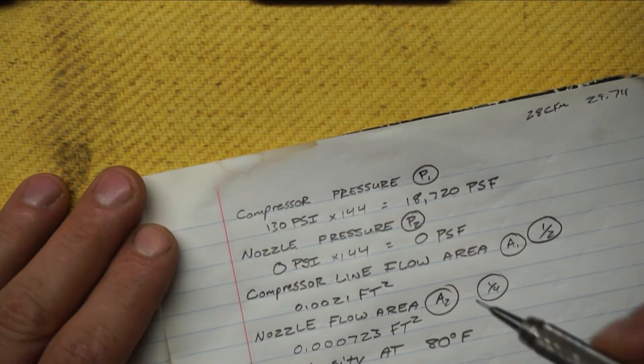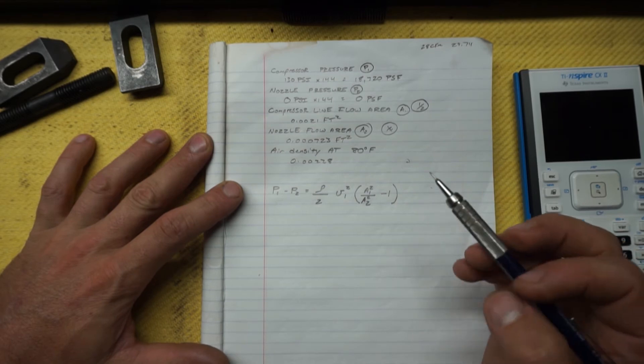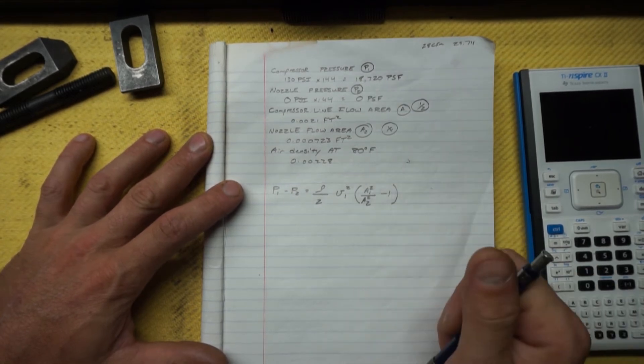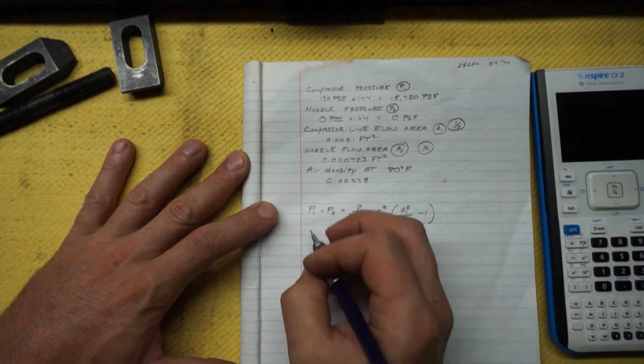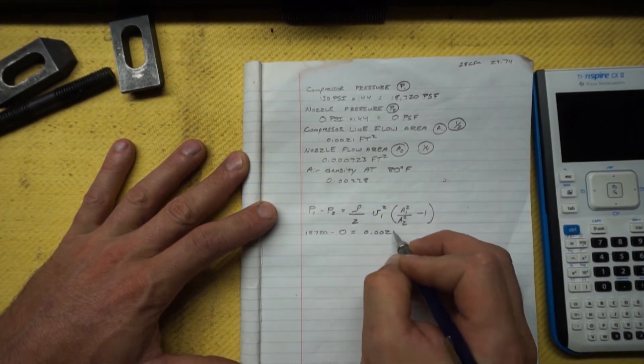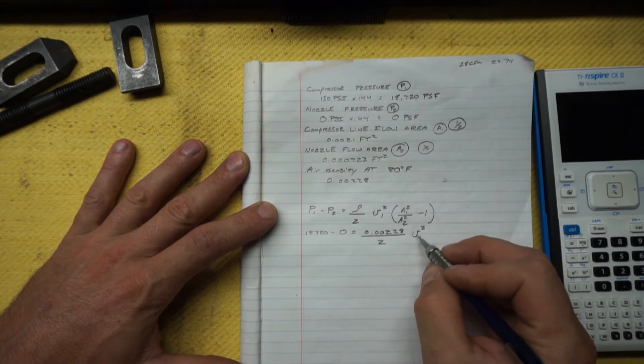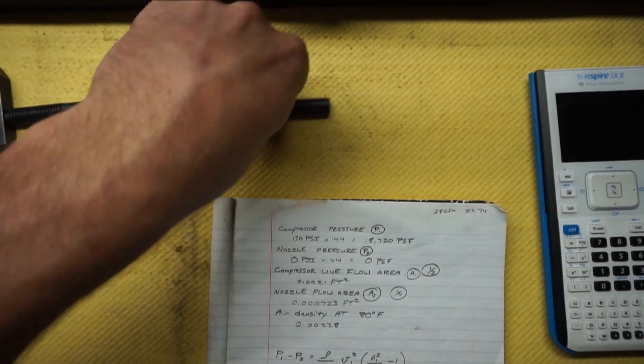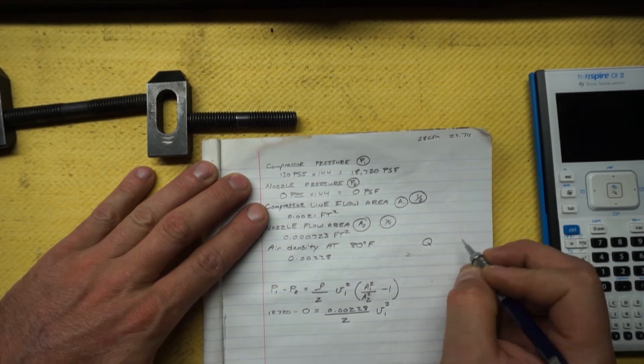So now we know we need to supply 130 PSI at all times to our nozzle, no matter what. How big should the air compressor be to supply at 80 degrees Fahrenheit, I need 130 PSI constantly in a wide open quarter inch pipe? Well that's where we start the math, and that's where this comes from. This is derived from Bernoulli's equation. We just start filling it in. PSF: 18,720 minus zero equals the density we found, 0.00228, over 2, v squared one. This is the velocity of the air at the compressor.